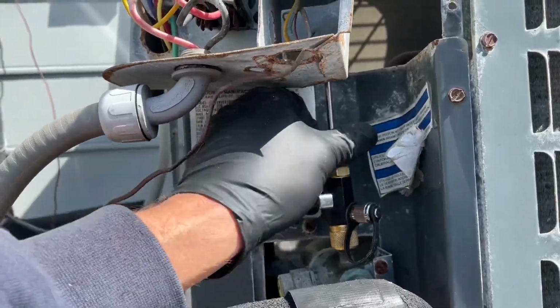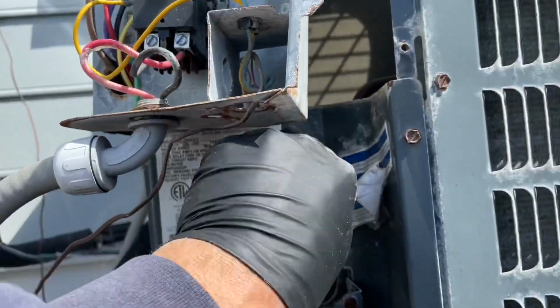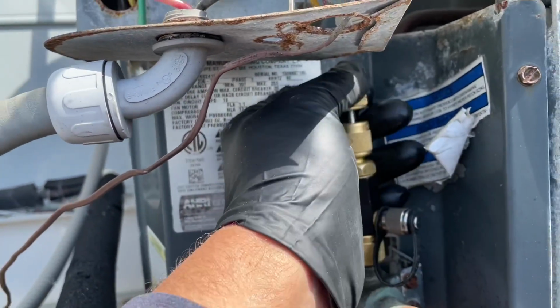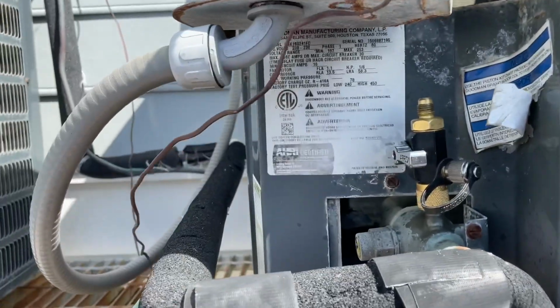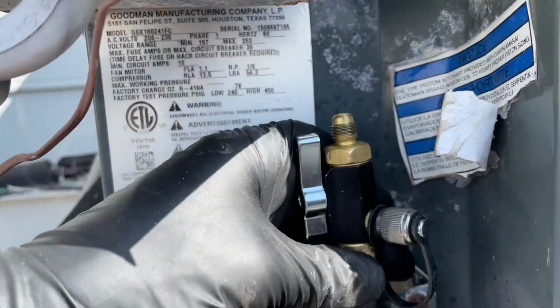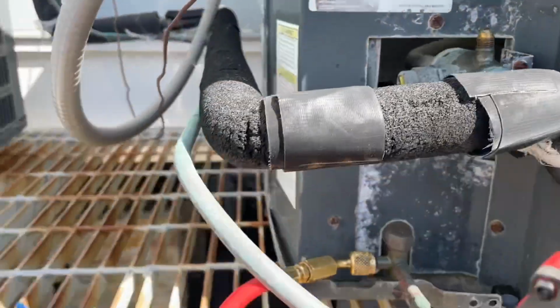Let's close this. Now, open, push down, and while you're pushing down, fighting the pressure, spin it until that core goes into place. Okay. Close the valve. I'm gonna take the top off to make sure she's good. I'm gonna open and we'll hear a little, just like that. See? Take off the core removal tool. And she's leak free. Look at that.